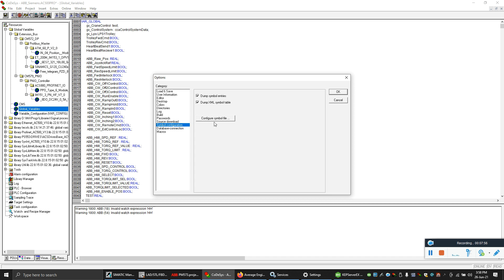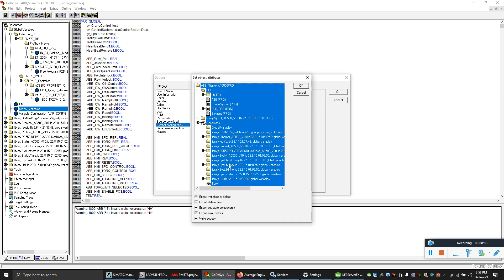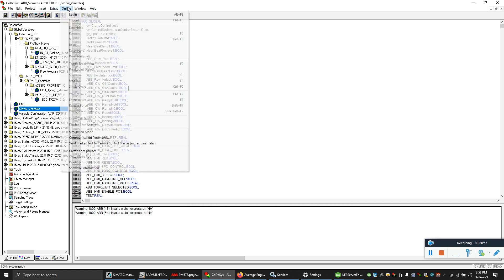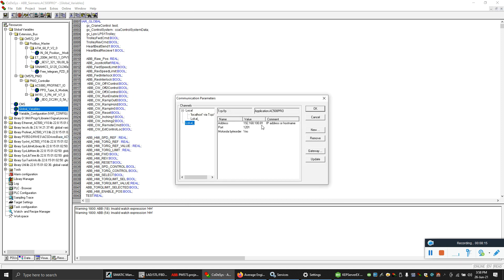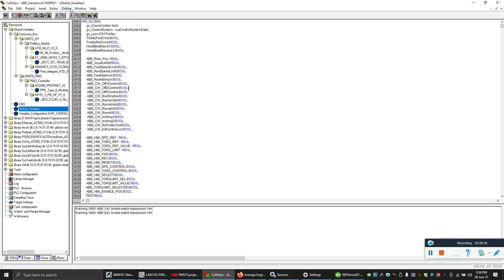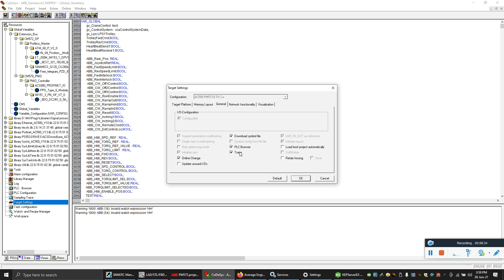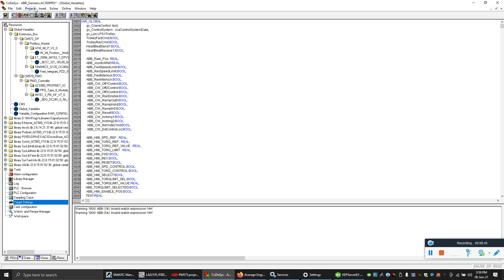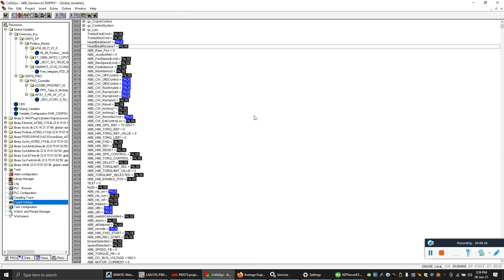Now let's configure the OPC server for ABB. Go to Project Options — in the simple configuration, click all this and select the entire project if you want all variables to go to your Codesys OPC server. Select all and click OK. In communication parameters, note down which address you are using to communicate with the ABB AC500 PLC. Then in target settings, click to download the symbol file — if you don't do this your OPC server will not work. Build the project, then go online and login.